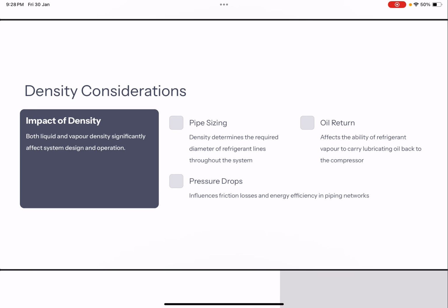Density, both the liquid as well as the vapor density, significantly affects the vapor compression system design as well as its operation. It is the density which determines the diameter of the refrigerant lines throughout the system. The pipes through which the refrigerant flows, their internal diameter, is a function of density. Similarly, the frictional losses and energy efficiency, because of the pressure drop, are also directly related to the density. Impacts of density could also be on the lubricating oil return, because you know that in the refrigeration system, the lubricating oil has to come back to the compressor, and this job is done by the refrigerant vapor.